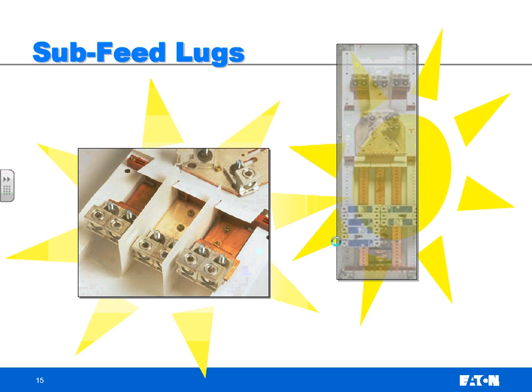Physically, in a panelboard, a mechanical lug is much smaller. So if you have to go to compression lug, whether it's an owner's requirement or what have you, you're usually going to get taller. And if you're talking on a feeder breaker, for all these breakers here I have, the only lugs you can get are mechanical lugs. What's the advantage of the compression?